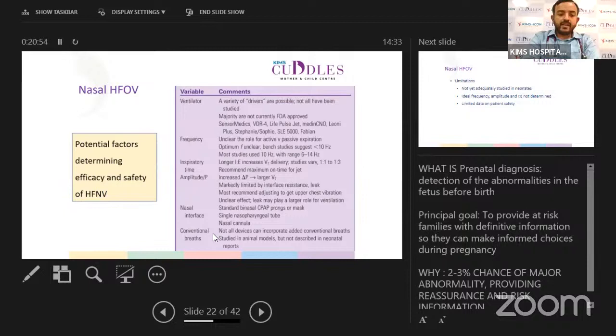Again, there is another idea suggesting application of conventional breaths on top of oscillatory breaths. This helps in providing sigh breaths. The frequency of sigh breaths can vary between 10 to 25. Again, there are no paradigms to allow us to understand if conventional breaths do provide additional benefit, and if they do provide additional benefit, what number of breaths should be delivered and what settings are to be used.